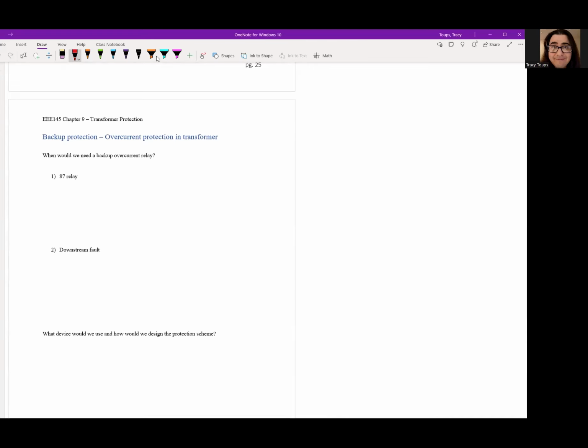So when will we need a backup overcurrent relay? When the 87 relay fails to operate, and it should. Now that could be because the settings were wrong, or some CT connection got messed up, or we had so many settings like restraint this, restraint that, harmonic this, slope 1, slope 2. There is a chance that you might mess up the settings. I mean, let's be honest, it's a very complicated system. So I'd rather have a tried and true overcurrent backup protection in case those settings got messed up.